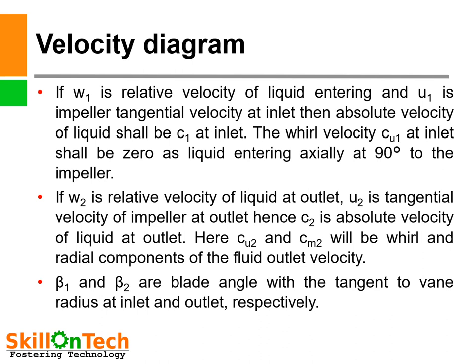We have seen the velocity diagram. If W1 is relative velocity of liquid entering and U1 is impeller tangential velocity at inlet, then absolute velocity of liquid shall be C1 at inlet. The whirl velocity Cu1 at inlet shall be 0 as liquid enters axially at 90 degrees to the impeller. If W2 is relative velocity of liquid at outlet and U2 is tangential velocity of impeller at outlet, then C2 is absolute velocity of liquid at outlet. Cu2 and Cm2 are the whirl and radial components of fluid outlet velocity. β1 and β2 are blade angles with the tangent to vane radius at inlet and outlet respectively.